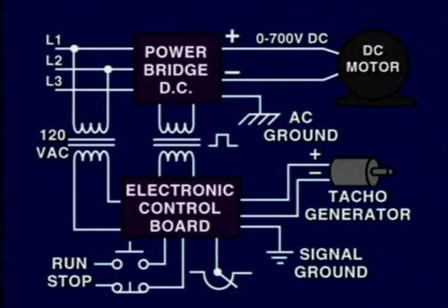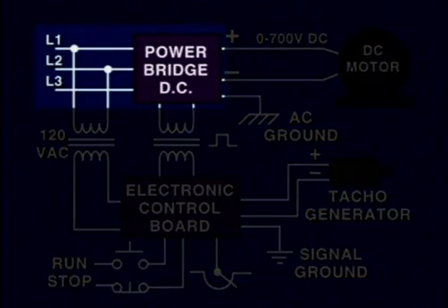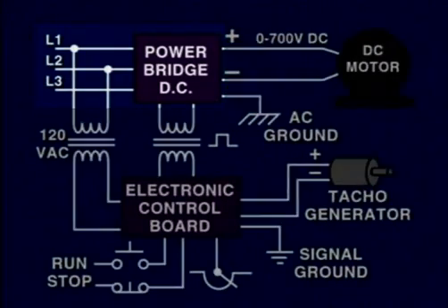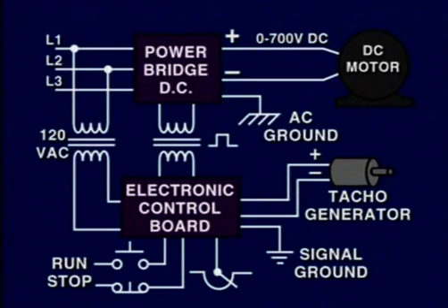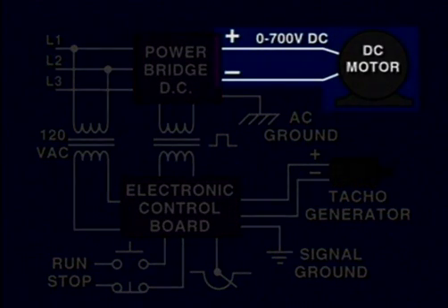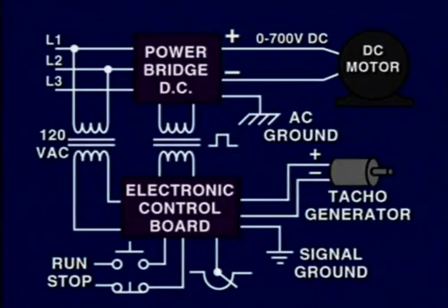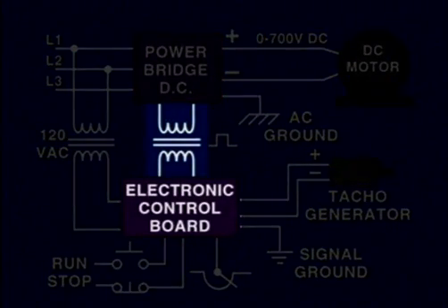In a circuit, 3-phase power may be delivered to a DC drive's power bridge. This power bridge rectifies the AC power for use by the DC motor. At the same time that the SCRs rectify the AC voltage, they control the amount of voltage applied to the armature, thus regulating its speed. This control is provided by an electronic control board which controls the firing of the SCRs.